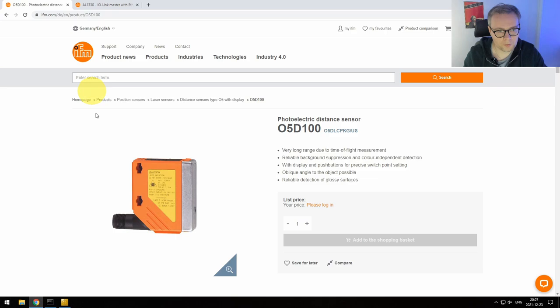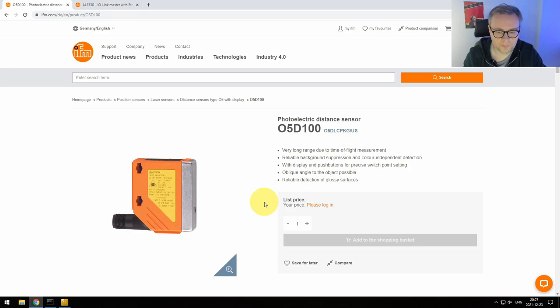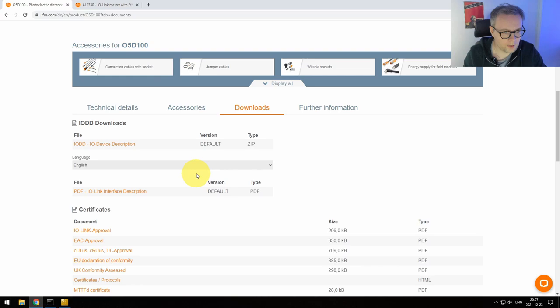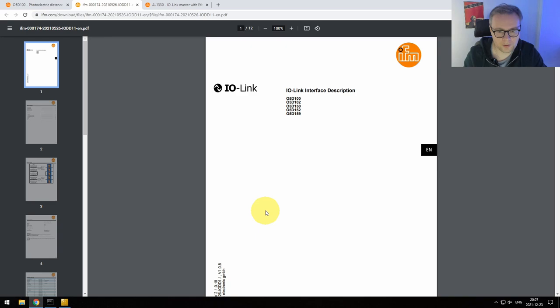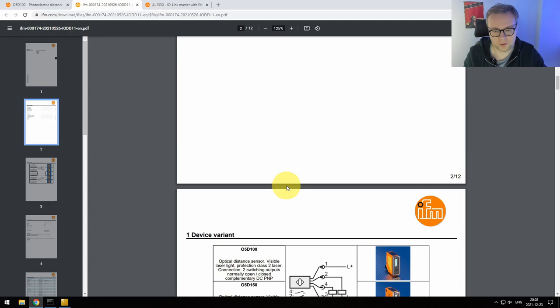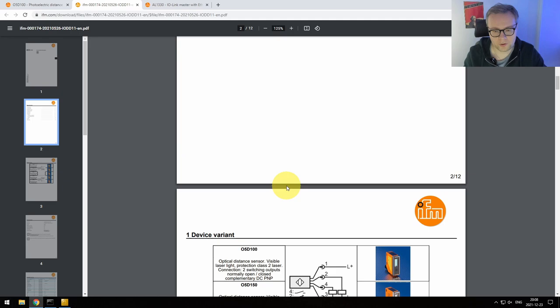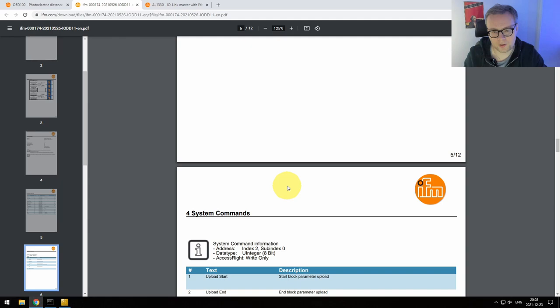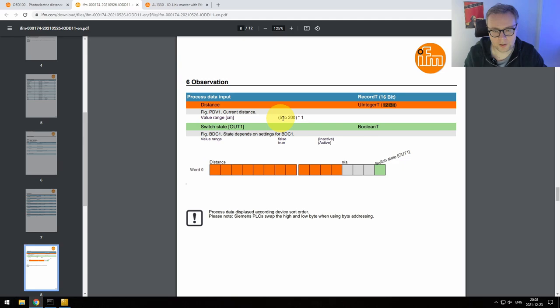Going to the sensor's IO-Link interface description PDF — this is the kind of document you'll read frequently when doing PLC software development. IFM's documentation is really good. Here we can see the process data input: a total of 16 bits, so 2 bytes. Of those, 12 bits represent the distance, with a value range of 5 to 200, meaning we can measure from 5 to 200 cm. There's also an extra bit indicating whether the value range is correct — basically whether the measurement is valid and can be trusted, which is useful to detect sensor displacement or dirt.